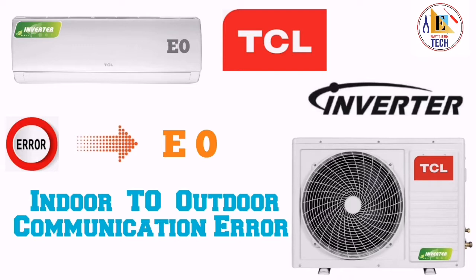Then we have to remove the communication cable from the indoor. Then again we check the DC voltage to see if it is between 13 to 24. If the voltage is not coming from the outdoor PCB, it means the communication coming from the outdoor to indoor is not perfect. Then we have to change the outdoor PCB, and our unit will be working.